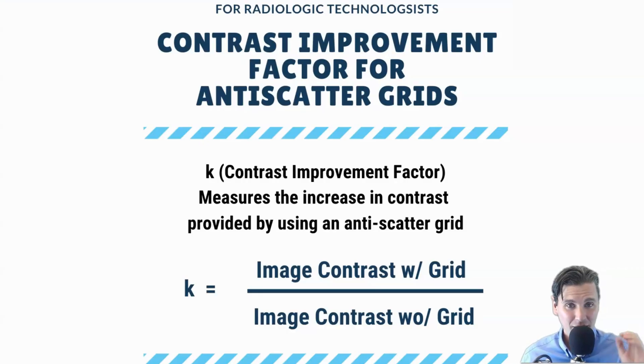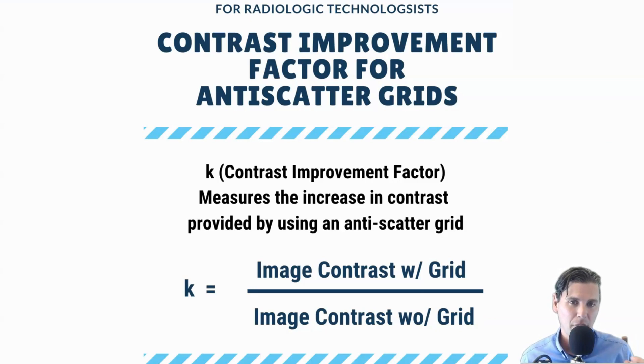We're also going to talk about the contrast improvement factor. That's the reason why we want to use a grid in x-ray imaging — to have higher contrast in our images. You're going to use a grid to reduce the background haze in your image, and the purpose of that is to get better image quality — image quality that you can quantify as better because it has a higher contrast.